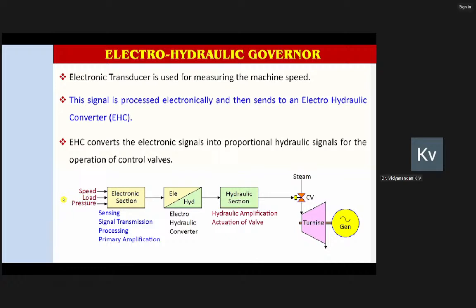Now here, all the signal sensing, processing, transmission, and primary amplification have been done electronically. But since the control valves are still hydraulically operated, we needed something called an electro-hydraulic converter, where we convert the milliampere or voltage signal of that particular transducer into a proportional hydraulic signal.